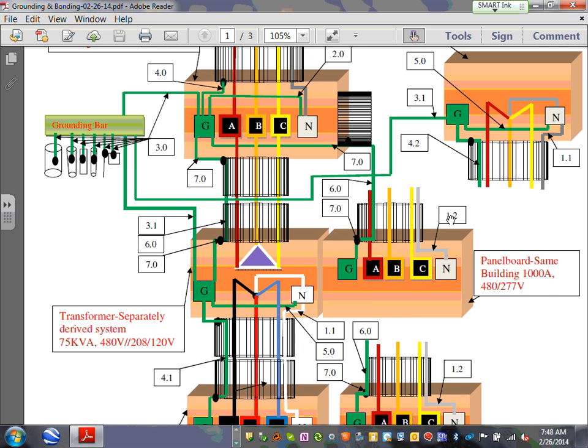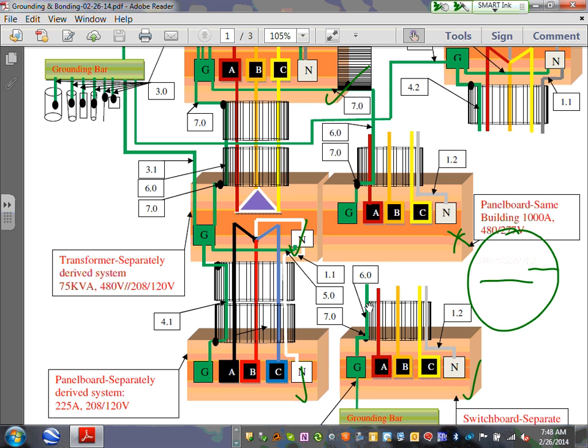Then, Karen, we took another feeder. Can you guys see right next to it, right here? Everybody can see that, guys? I have another panelboard in the same building. I can't emphasize enough the words 'the same building', because, Adam, if the panelboard is in the same building, grounding and bonding will be unique. So here's my service. From the service, I took a feeder to feed a transformer that feeds the panel. Then I took another feeder that feeds another panel inside the building, and a third feeder to feed another panel.